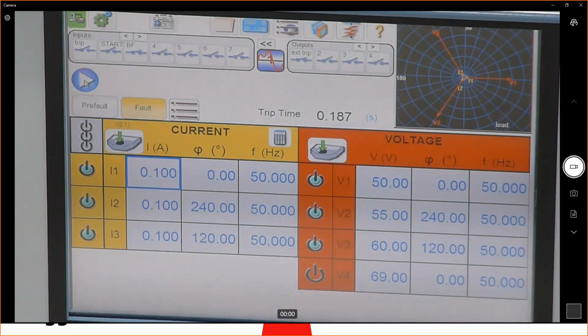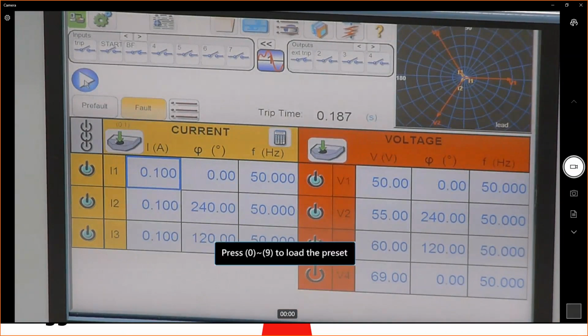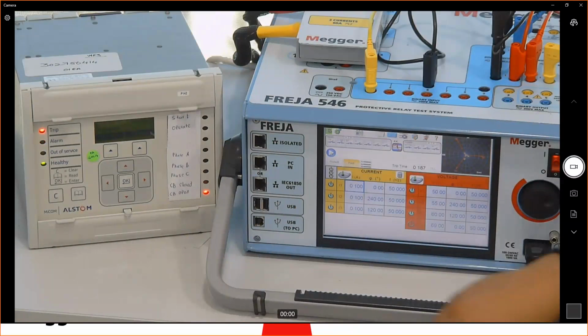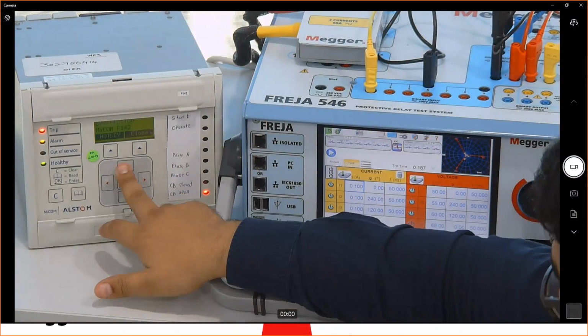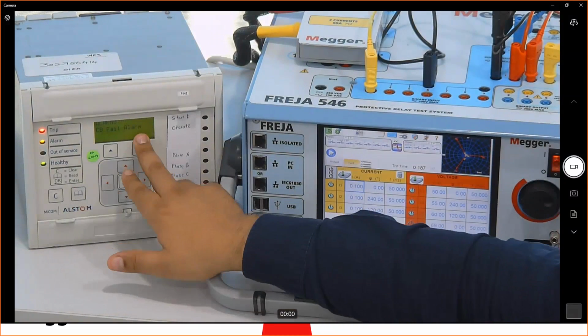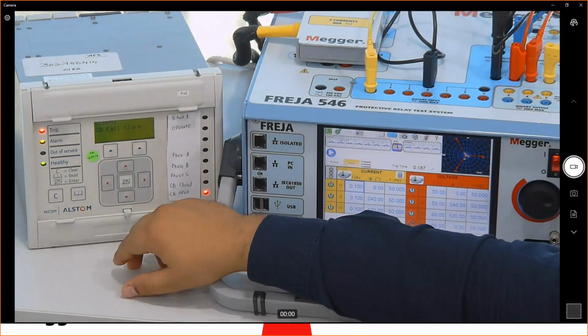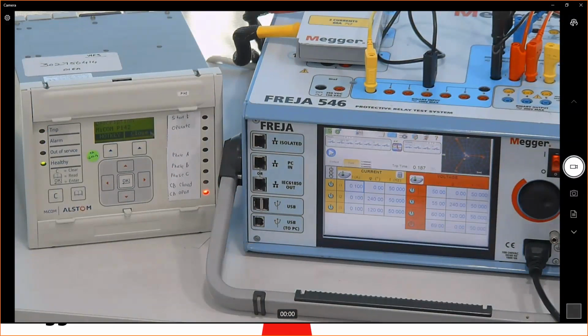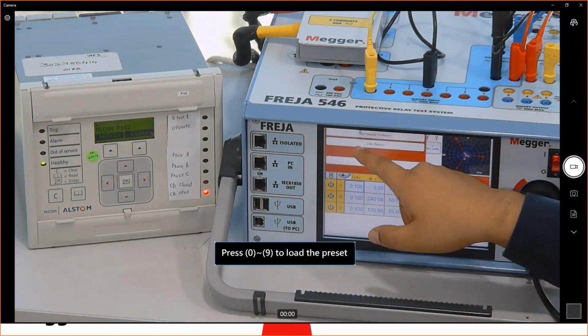Right. And also there is an alarm on my relay showing me that the breaker failure has operated. Let me show. Click here, go back. Click here, CB fail alarm means the CB failure has operated inside the relay as well. So I can reset that alarm, no problem. So now I have tested the timing. I got the timing.